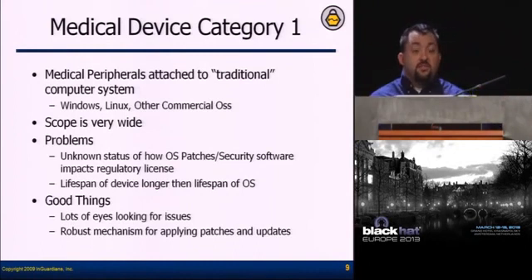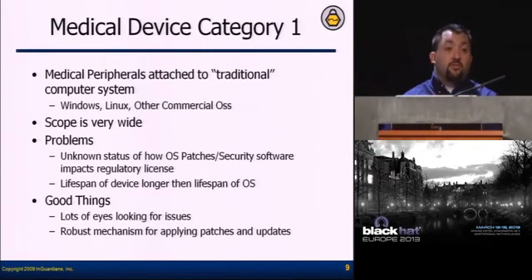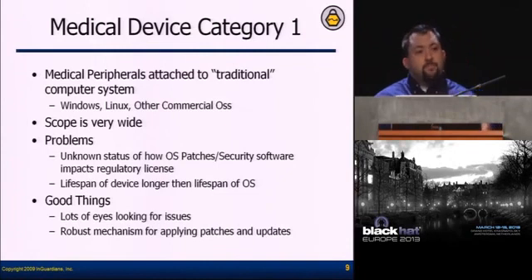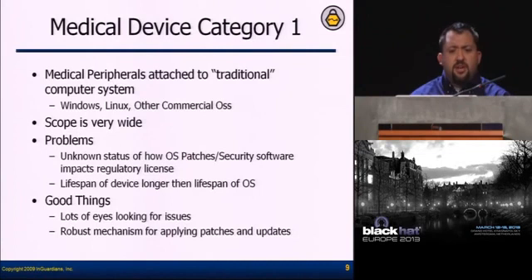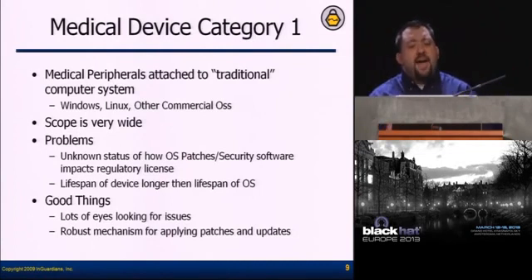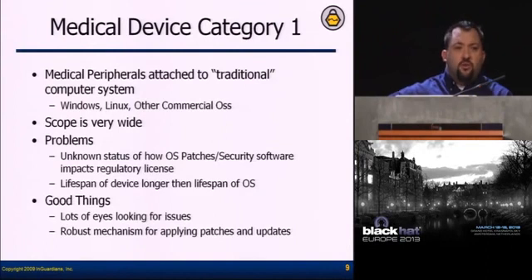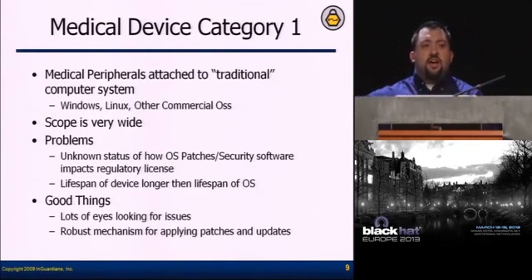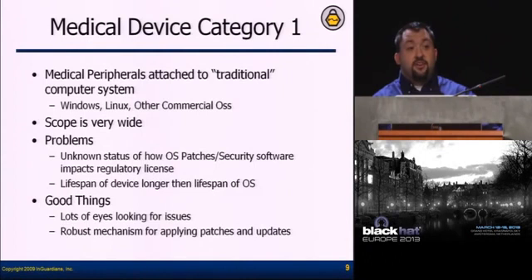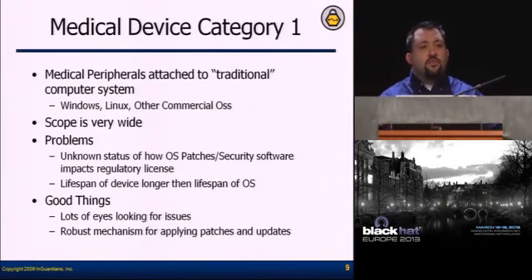It covers more and more, and hospitals are using devices that have a Windows-based operating system or a Linux-based operating system on their devices. And one of the problems which many companies and hospitals have come to me about is they don't know how the status of patching and securing this software impacts the regulatory license of these. So if you buy a medical device from Acme and it goes through the approval process running Windows XP Service Pack 2 with patches up to date, and then 2 years down the road, the hospital says, well, this device in our pen test showed as being insecure. Can I apply patches to it? And Acme, the vendor, says, no, no, no. If you apply patches to that, first of all, we would not service that unit anymore because we haven't tested that. But second of all, when you patch the device, it puts the regulatory approval in question.